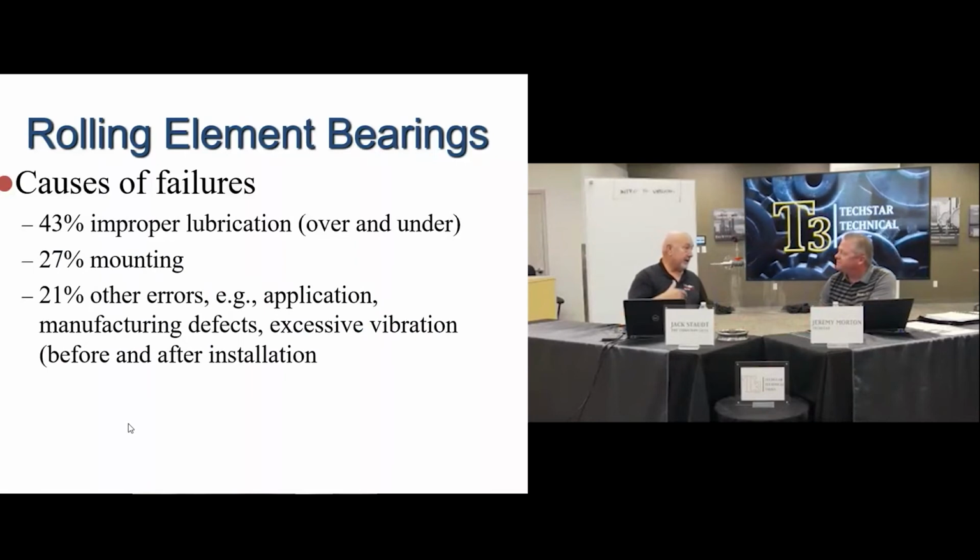I had a company in Odessa that was building pumps and having bearing failures, and they asked me to come out and see if I could find out what was going on. First thing we did was cut one of the new bearings open and do an analysis on it, and we actually found some issues.